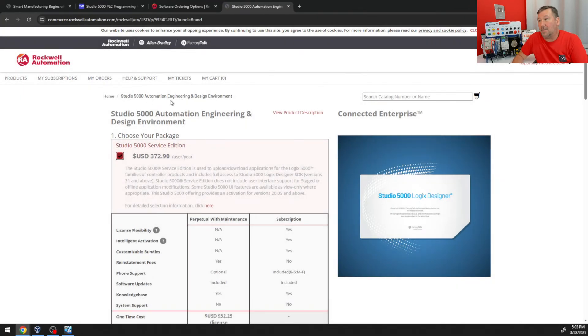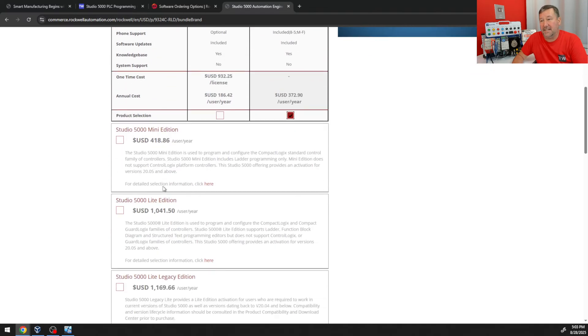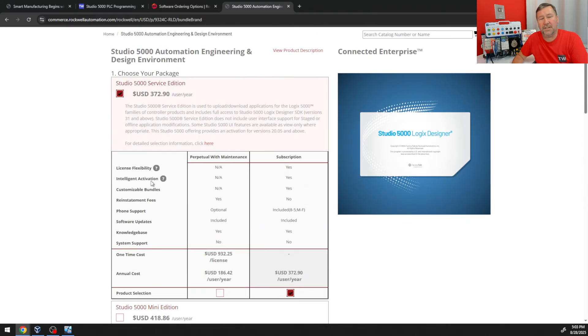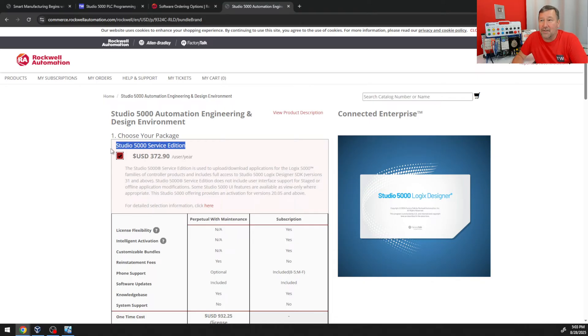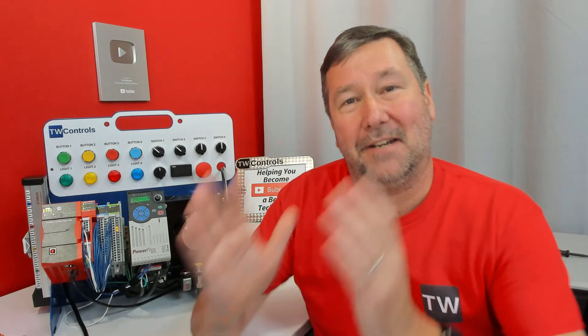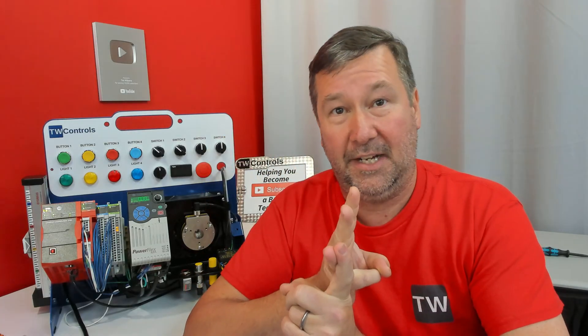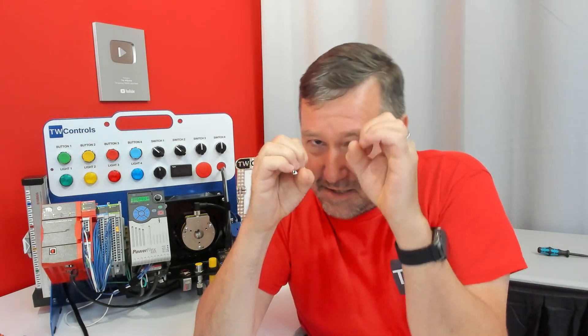Right away we're going to see the different options: Service Edition, Mini Edition, Lite Edition, and so forth. I have a very strong opinion of Service Edition. Robert said he likes Service Edition because you can download, toggle, and force. And I said I don't like Service Edition because you can download, toggle, and force. My objection is you're giving someone just a small peek into the software, but you're not teaching them enough not to be dangerous. If you want someone not to mess up when troubleshooting a machine, you want them fully understanding the software — and I don't think you can get there with Service Edition.